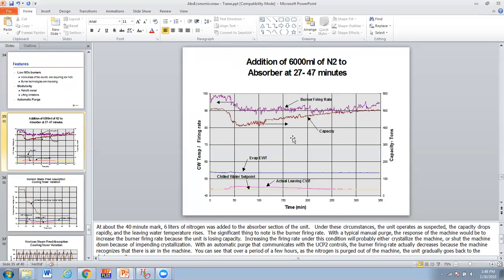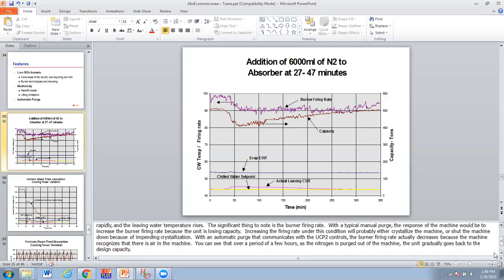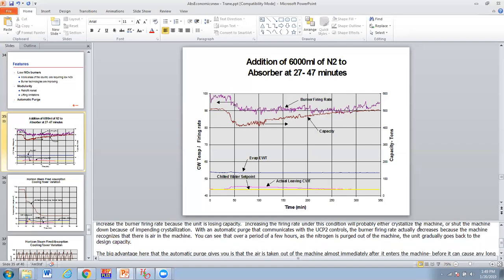Significant to note is the burner firing rate. In the past, with a typical manual purge, the response of the machine would be to increase burner firing rate because the unit is losing capacity. Increasing the firing rate under this condition will probably either crystallize the machine or shut it down because of impending crystallization. With an automatic purge that communicates with the controls, burner firing rate actually decreases because the machine realizes it's had a leak. Instead of increasing burner firing rate and keeping it high, it drops it back because it could well crystallize.